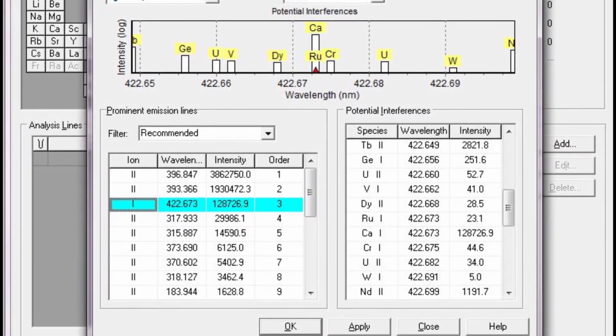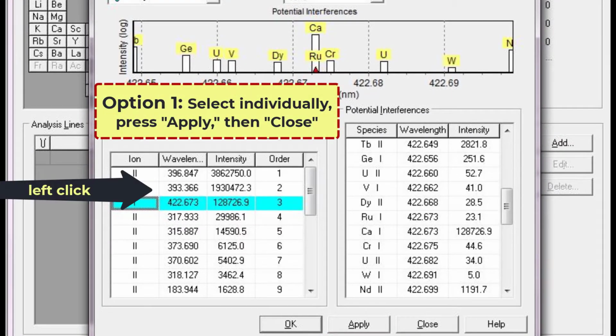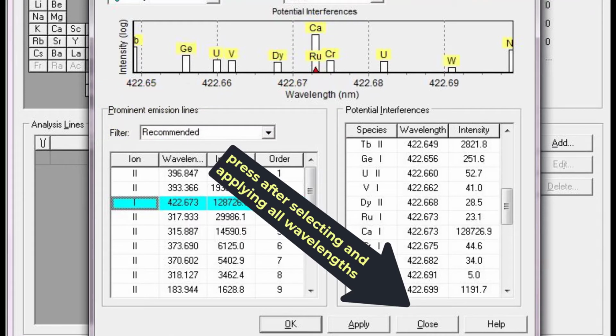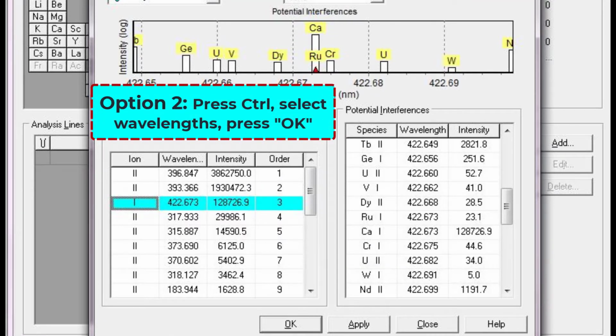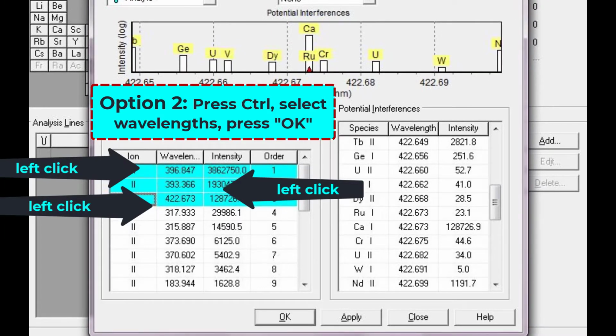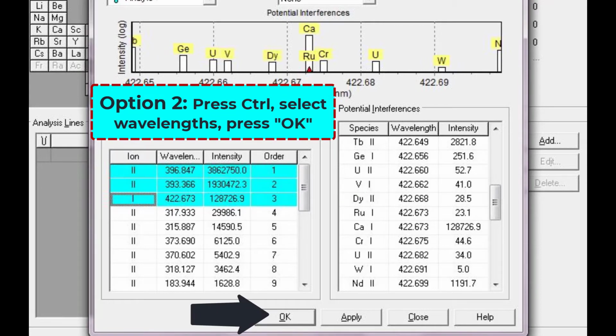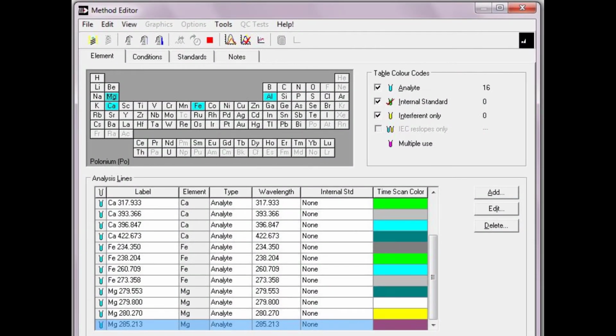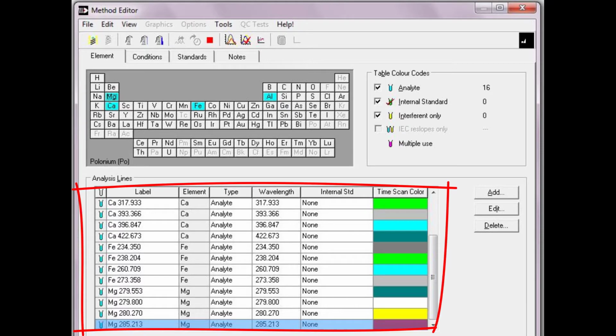We suggest selecting 3 wavelengths for every element you will be measuring. There are 2 ways to do this. First, you can left-click and then press Apply to add them one at a time. In this case, you would make your selections and then press Close. Second, you may hold down the Control key, select your 3 choices one at a time with a left click, and then press OK. Repeat this process for each of the elements you will be measuring. You'll see each atom will be highlighted in blue on the table, with all of the wavelengths listed below.